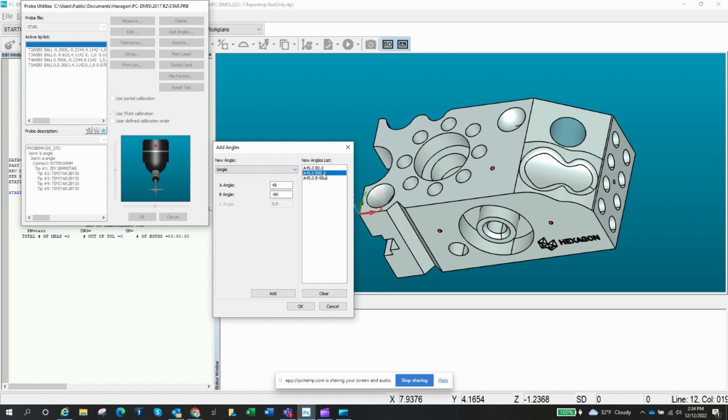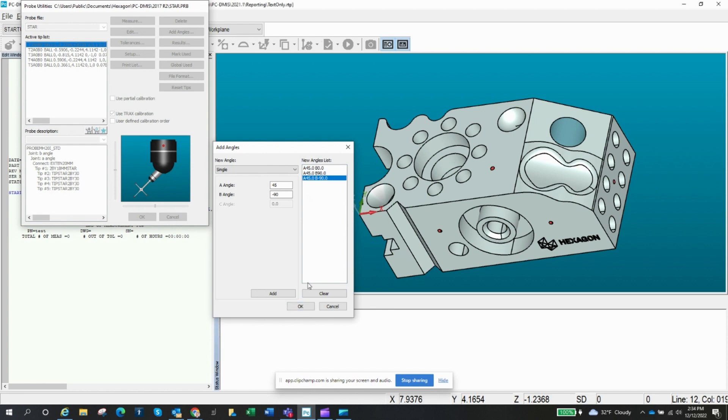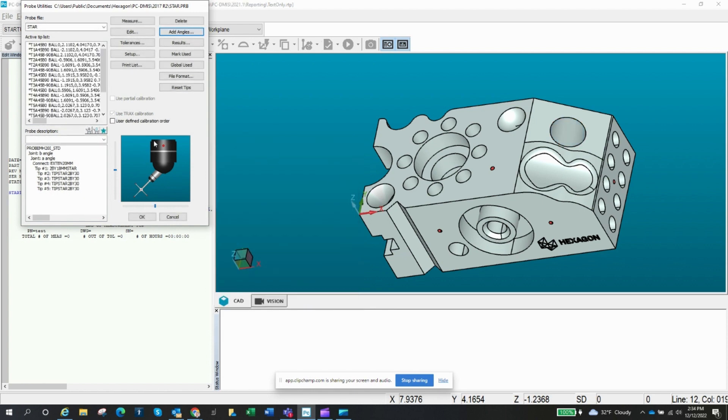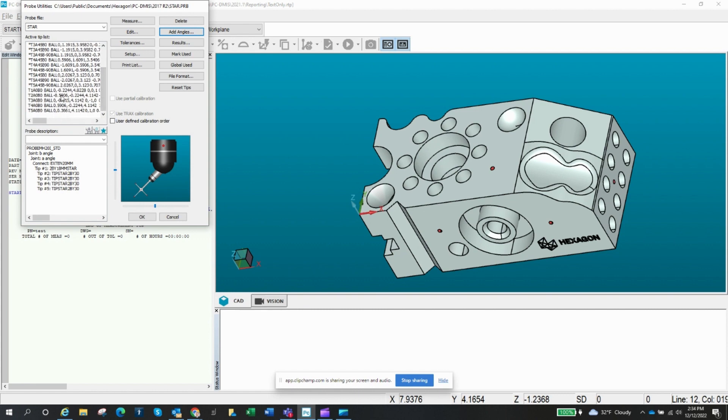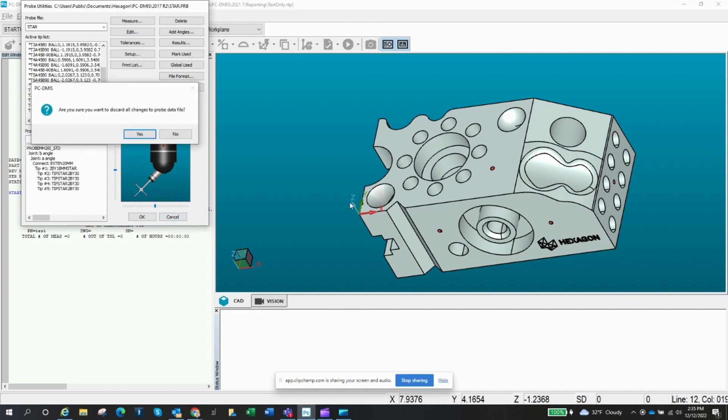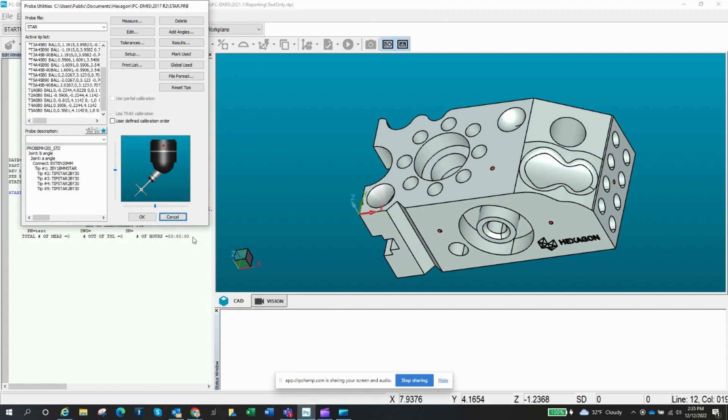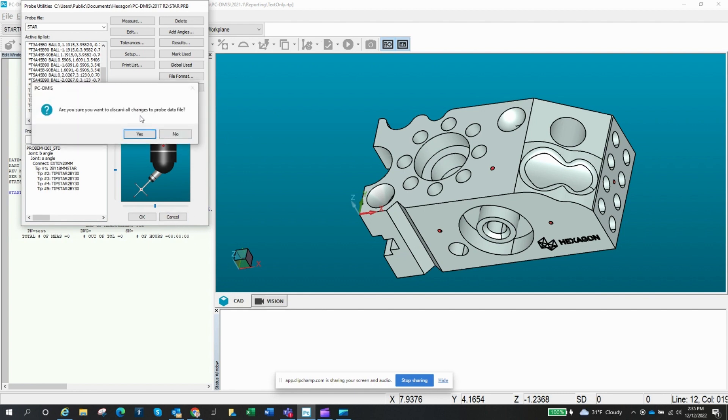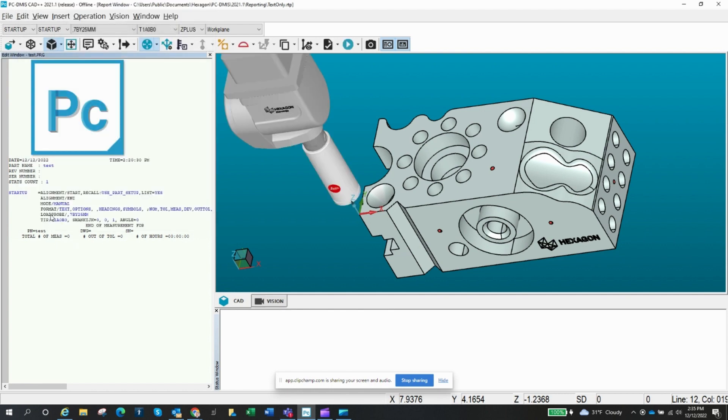And that may not be the right angle, but that's okay. It gives us pretty close. So we can go in and we can delete that one out, and then we can add those. When you add those, you notice that it's going to add all those tip angles. You're going to have to add all of them. Now you may not need to calibrate everyone because you may not be using them, but it is going to add every tip angle. So if you think about a 45 by 90, it's going to do tips one, two, three, four, five of that tip angle. So hopefully that makes sense. Let's go back to, I'm going to hit cancel. Let's get rid of that just so it's a little cleaner. We don't want to save that. Yes, I'm going to discard that.